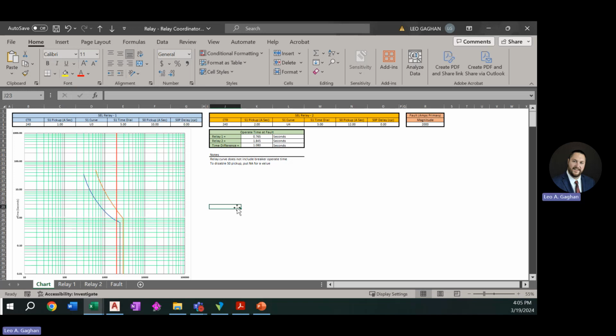for a certain fault. So let's say this was it, right? Let's say we had set up device 1 as such, and we were trying to reconfigure device 2. With that time dial down, so we actually have a challenge here. There we go. Okay. So let's say we had device 1 configured as such. We needed to alter device 2 to maintain a certain time difference. And we knew that the fault magnitude was going to be 2,000 amps. Let's say our client has specified that they need 300 milliseconds of time difference, right?